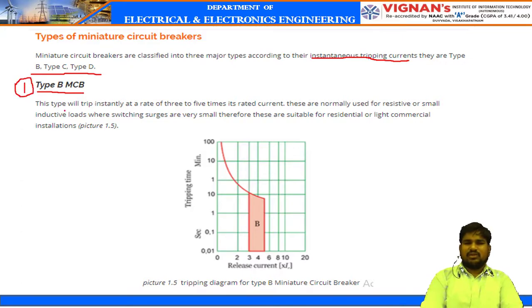In this type, the trip is instantly produced at 3 to 5 times the rated current. That means this MCB is rated to withstand 3 to 5 times the rated current. These are normally used for resistive or small inductive loads where switching surges are very small. Therefore, these are suitable for residential or light commercial installations. Right, so observe here, this is the main point.